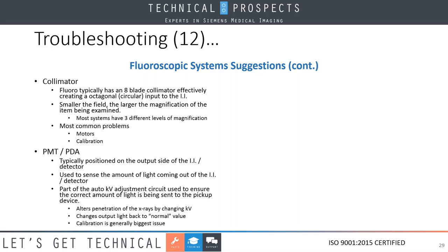Some other things to consider are your photomultiplier tube or photodiode array. All right. These are typically positioned on the output side of the I.I./detector. And this is what's used to sense the amount of light coming out of the II or detector. All right. As we go over different body parts, this is what the output of the II or detector is going to change. Once this device senses that, it sends a signal to the generator to either increase or decrease the KV based on what it's seeing. All right. One of the biggest problems here is people fail to calibrate this properly.